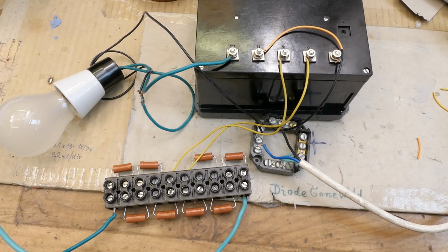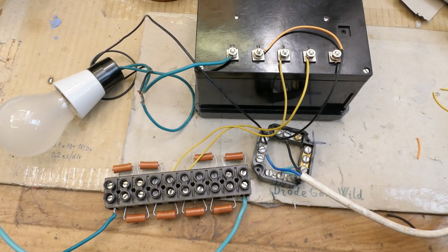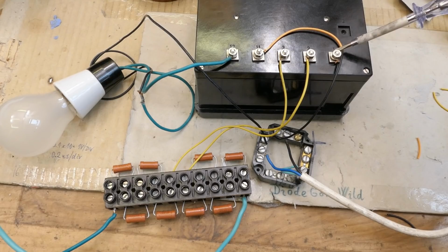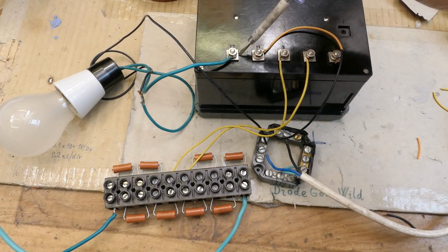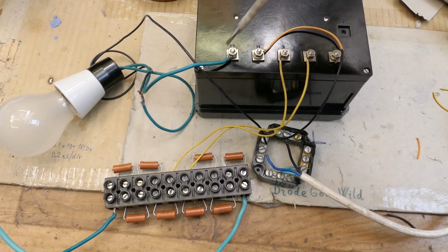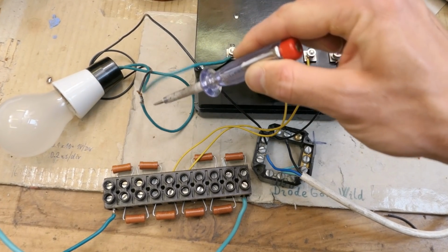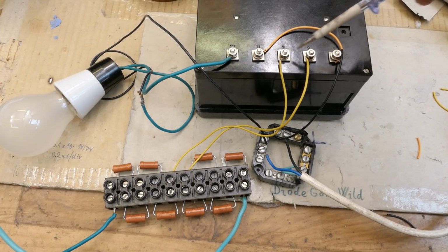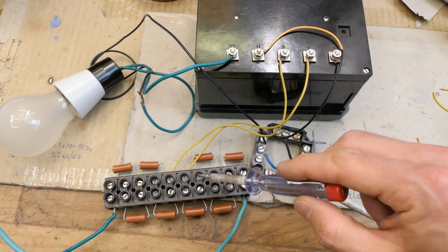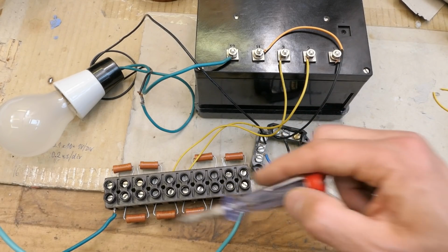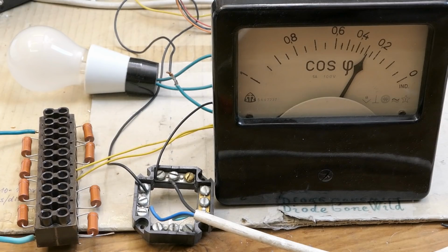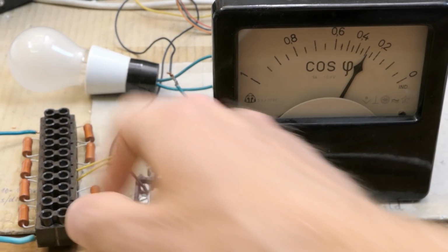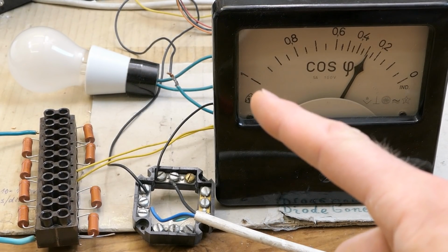So here is the dodgy wiring. The phase where I am connecting the load goes to the common terminal of both voltage coils and also to the current coil. And the other terminal of the current coil goes through the load to neutral. And then the terminals of the voltage coils go to the other 2 phases via resistors. These are the other 2 phases. And let's power it with a 40 watt lamp. And it should indicate 1 on this scale.